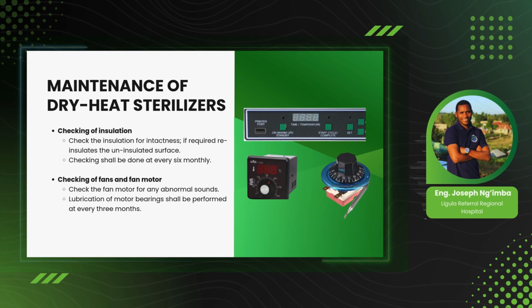Yes, let's check another thing that we do in maintenance. We check the temperature controller. We check the display to see that it displays correctly, with no blinking, and that it is not failing to display at all. If the display is not displaying well, or not at all, we will have to replace it. We check the connection between the wires and the display or controller, because we have different kinds of temperature controller, the digital one and the manual. If there is any looseness, we make sure they are connected tightly. This maintenance is checked on a 6 months basis.